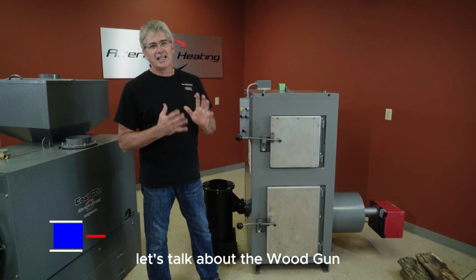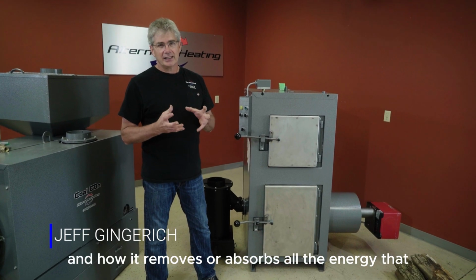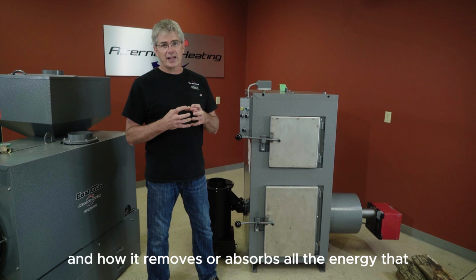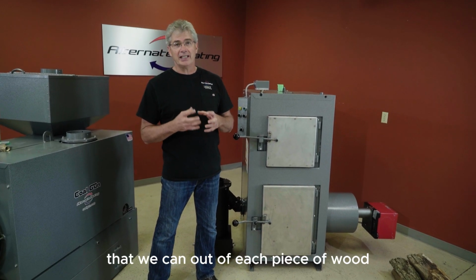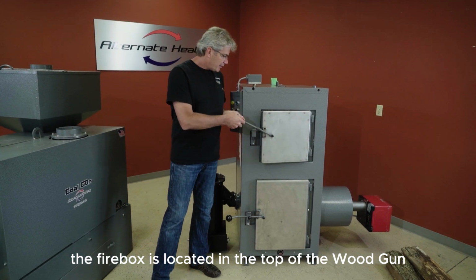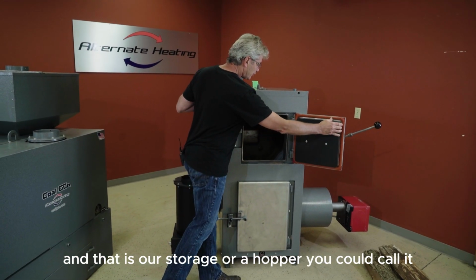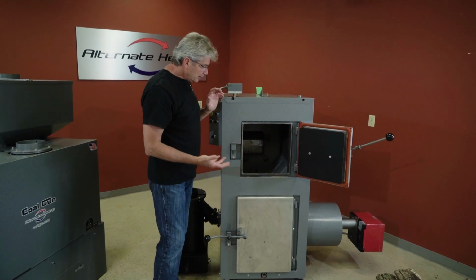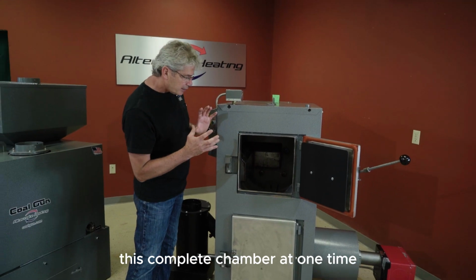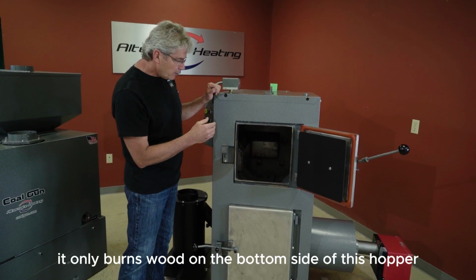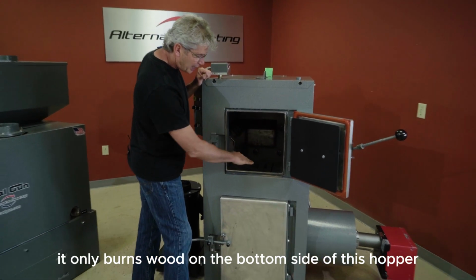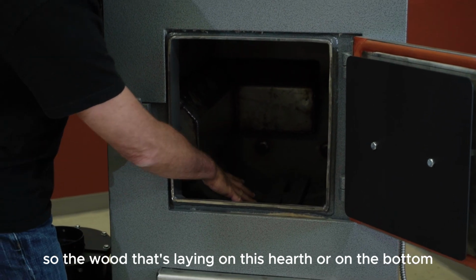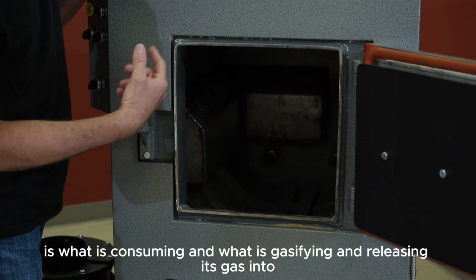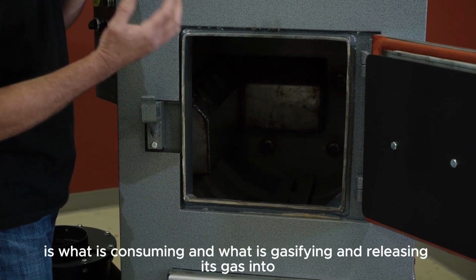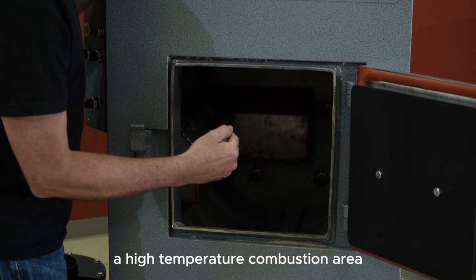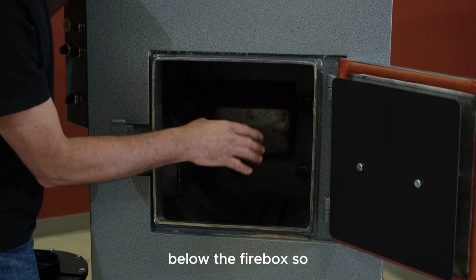Let's talk about the wood gasification boiler, and how it removes or absorbs all the energy that we can out of each piece of wood. The firebox is located in the top of the wood gun, and that is our storage, or our hopper, you could call it, because it does not burn this complete chamber at one time. It only burns wood on the bottom side of this hopper. So the wood that's laying on this hearth, or on the bottom, is what is consuming and what is gasifying and releasing its gas into a high temperature combustion area below the firebox.